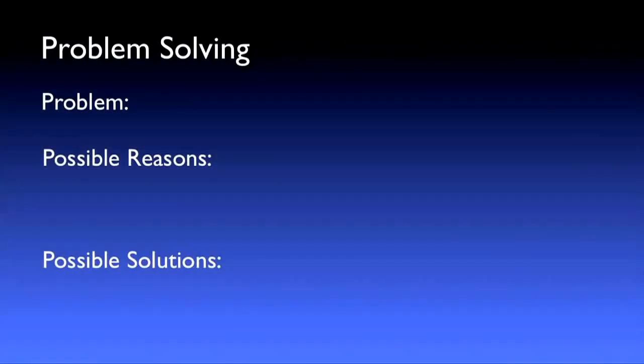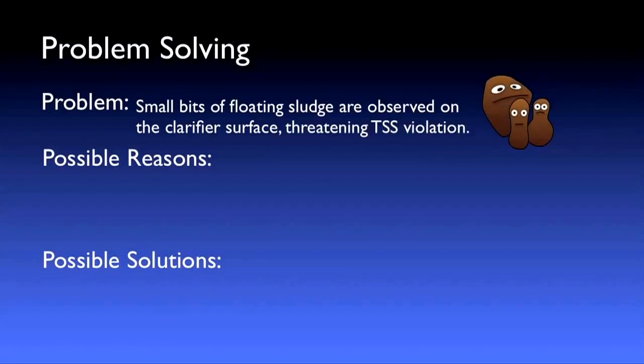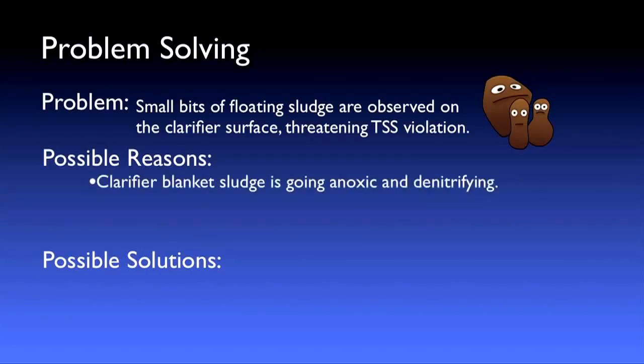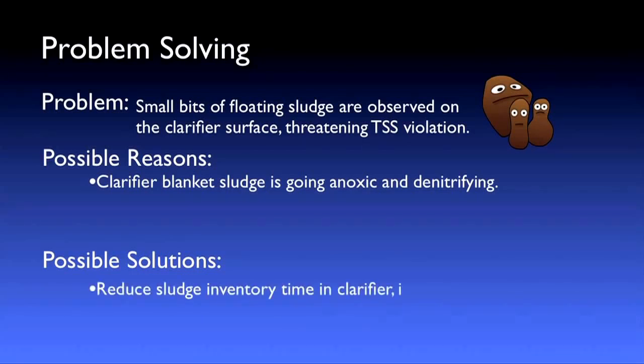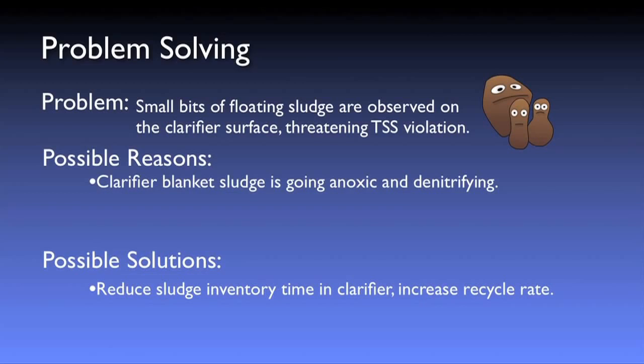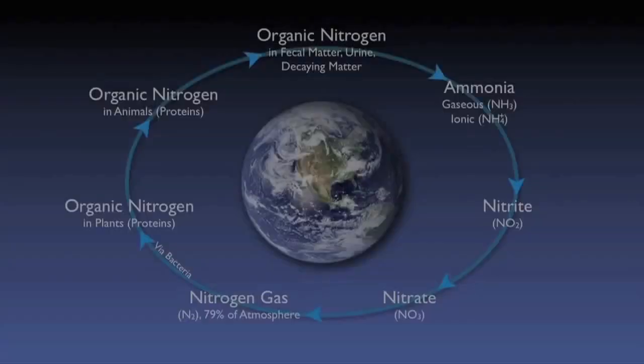Finally, during your afternoon stroll through the plant, you notice small bits of floating sludge accumulating on the surface of the clarifier. It becomes obvious that your sludge blanket at the bottom of the clarifier is going anoxic and denitrifying, causing sludge to float due to the generation of nitrogen bubbles. Letting instinct take over, you spring to action by increasing the recycle rate, reducing sludge inventory time in the clarifier and preventing this unwelcome denitrification.